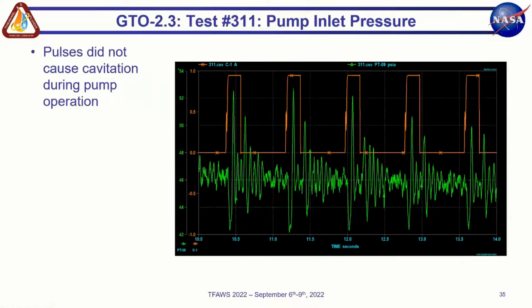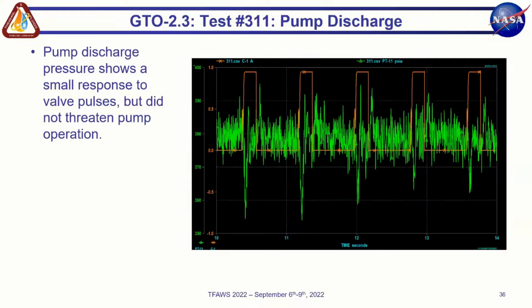Even with these longer pulses and more thrusters, we fortunately did not encounter cavitation during pump operation, and this was one of our major concerns as we were designing the systems. We were unsure if all of the different valve transients downstream would end up causing cavitation at the pump inlet. Fortunately, we were able to avoid cavitation through our system as it was built. And in the same way, there is a measured response to the thruster firings, but again, nothing that the pump couldn't handle.